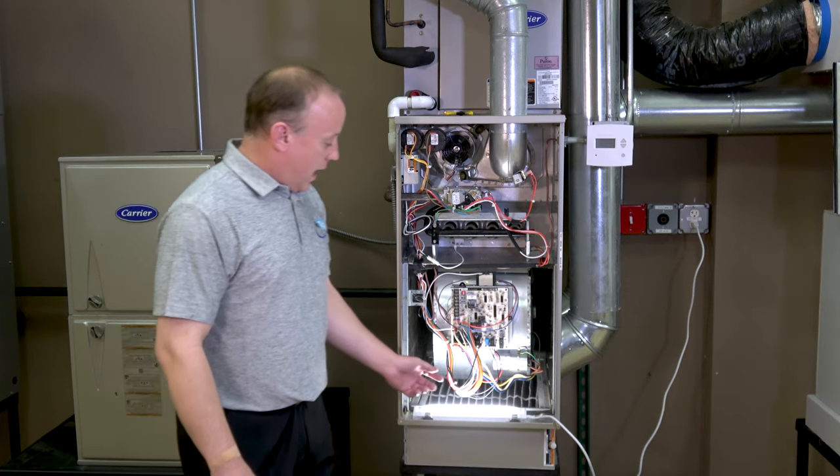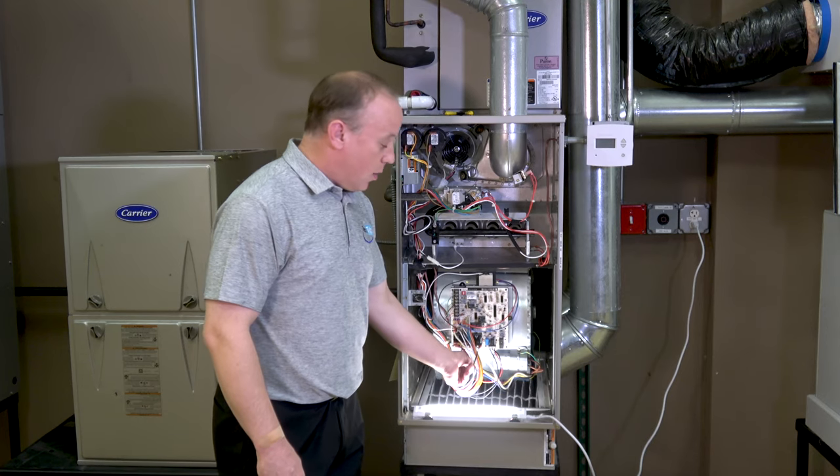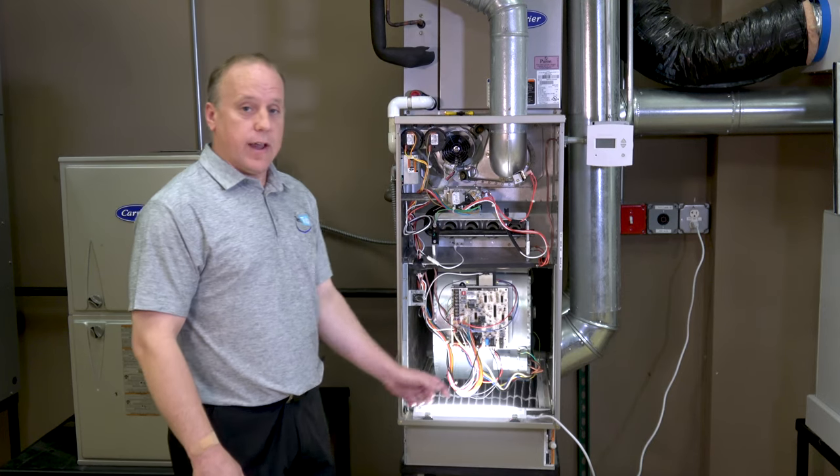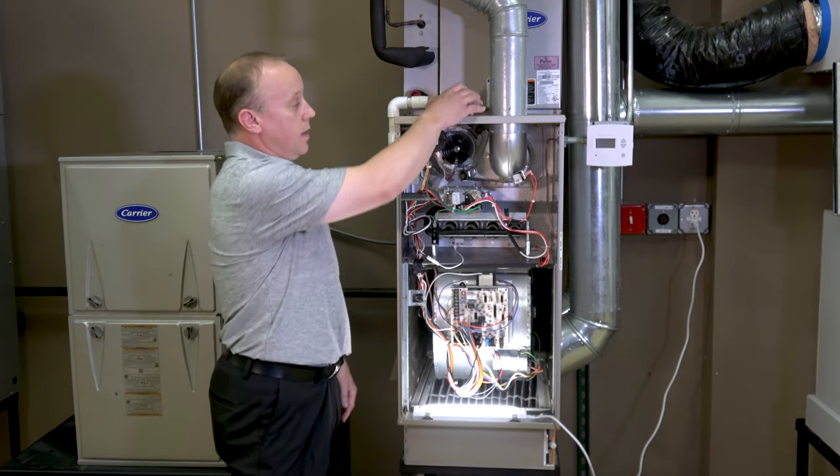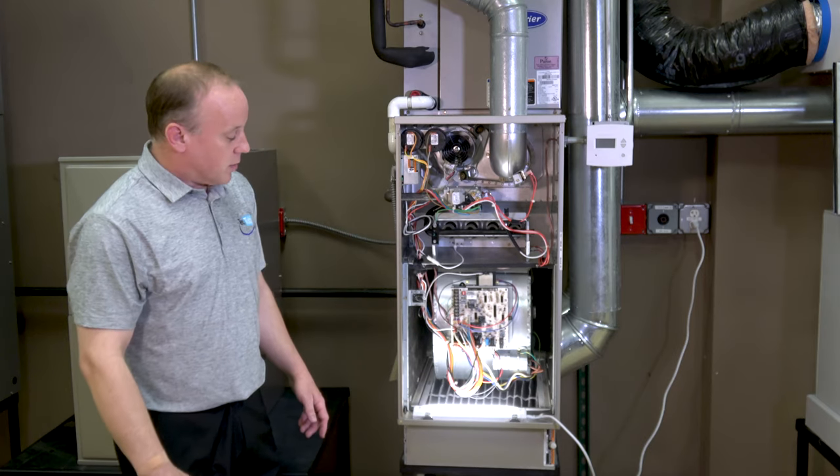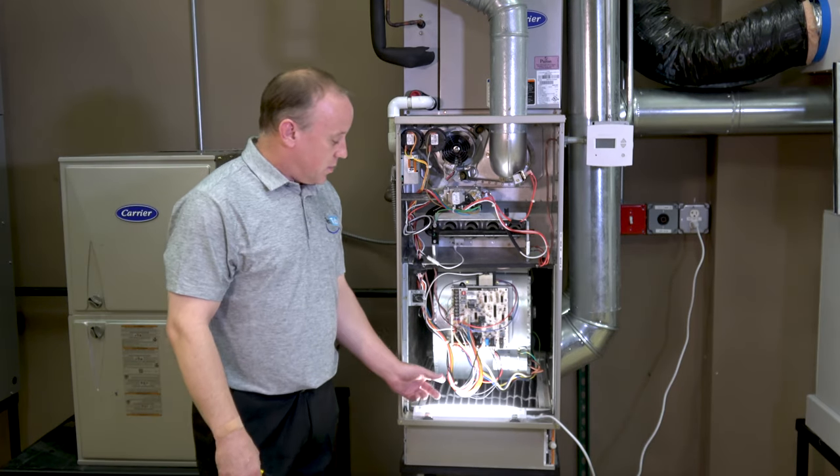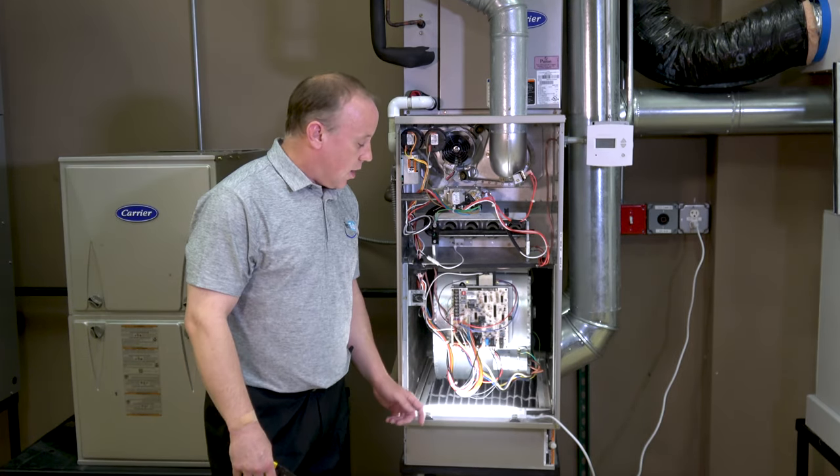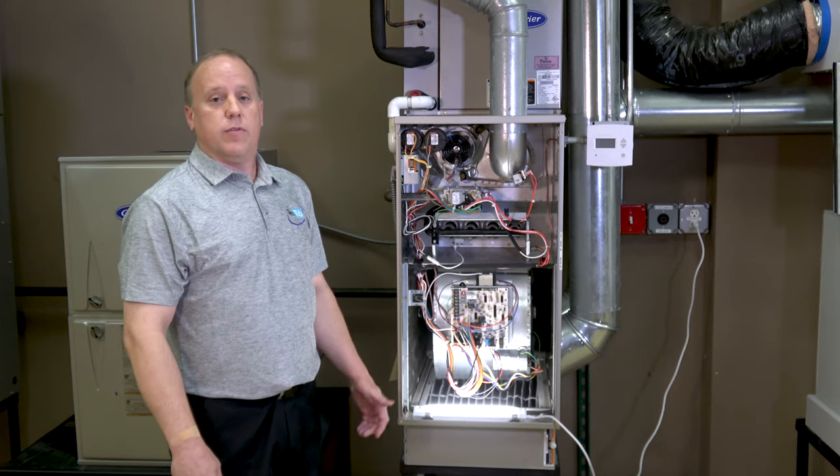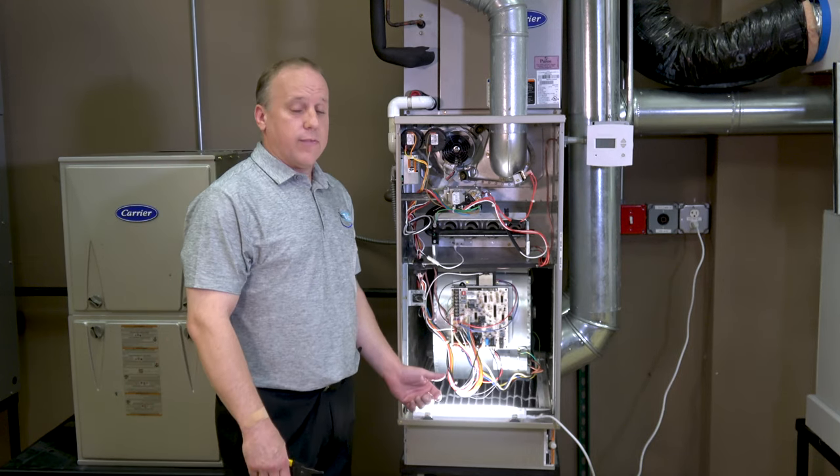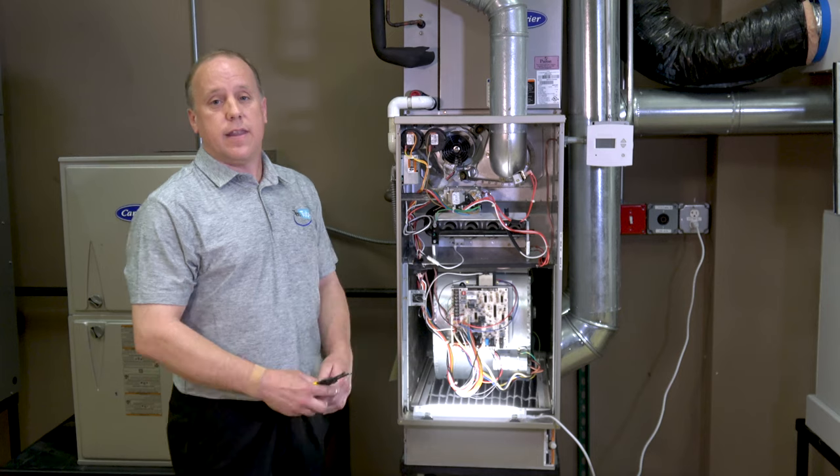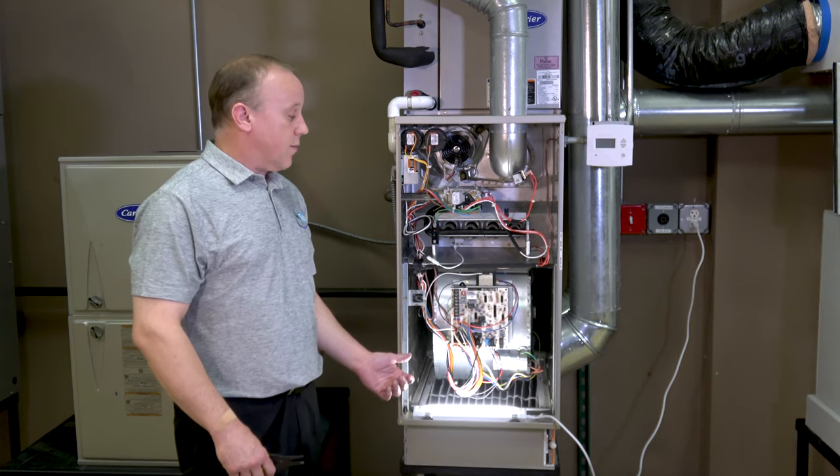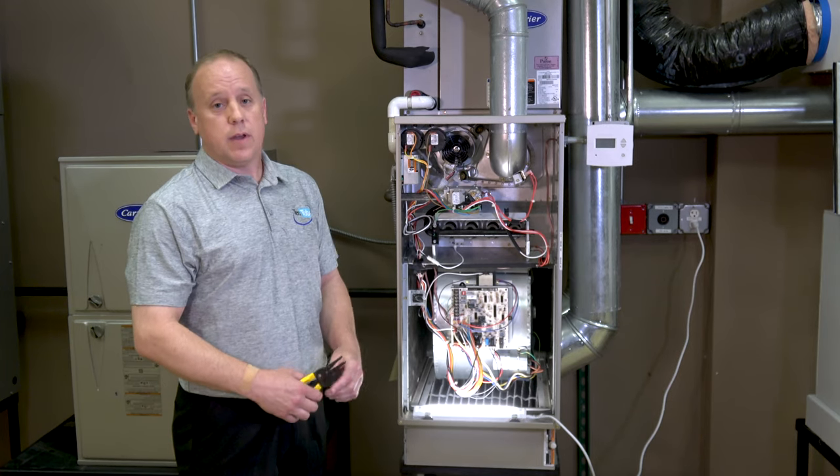This motor on this furnace is a four-speed motor so you will have one extra speed that will be hooked up to a spare terminal. As far as the speed settings go, depending on what you would need for the CFM to move enough air through the furnace, you would have to reference the product data and that would also be affected by the static pressure in the system.